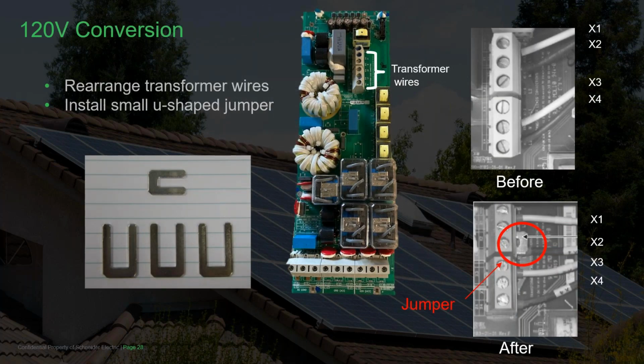Each XW Pro ships configured for 120/240 split phase by default. For a three-phase system, each XW Pro must be converted to 120 volts. This is accomplished by installing the jumpers. There are 3 large and 1 small jumper that are supplied in the bag of hardware that ships with each XW Pro, which also includes brass DC terminal fasteners, a 5-pin Phoenix connector for the aux port, a battery temperature sensor, a foam air filter, DC terminal covers, and a network terminator for Xanbus. Please don't throw the bag away because that hardware is not sold separately.